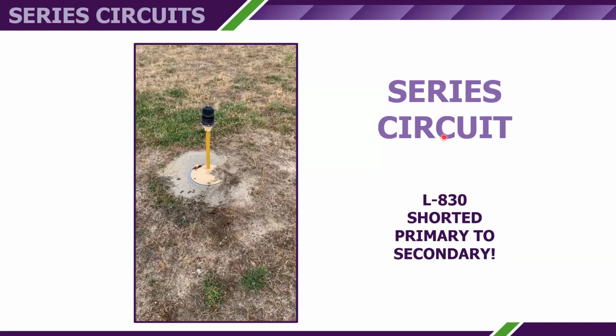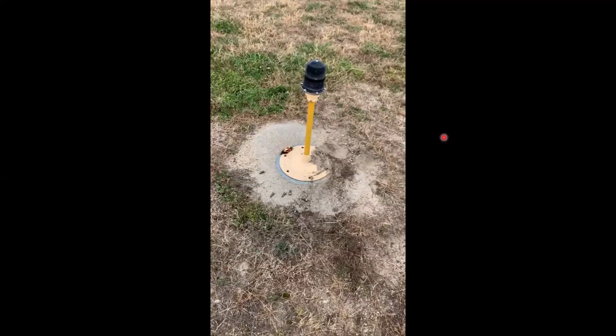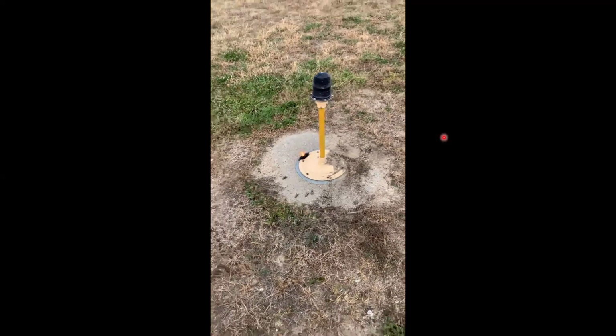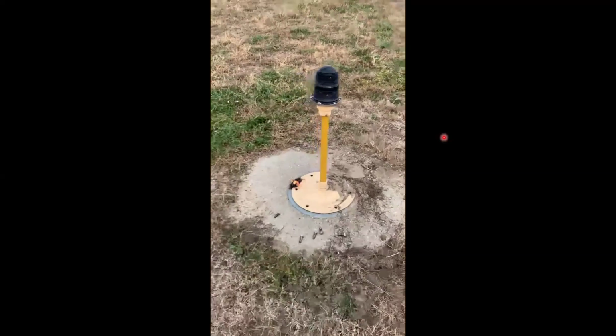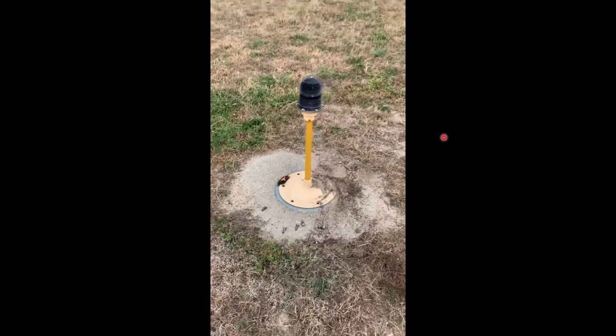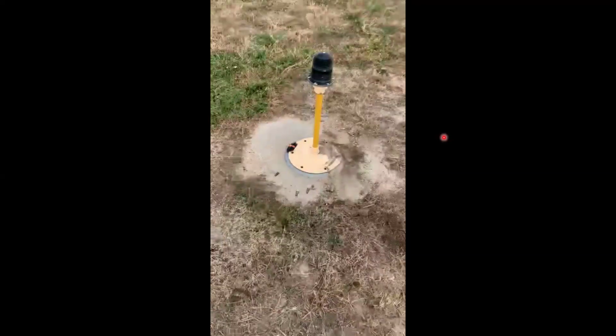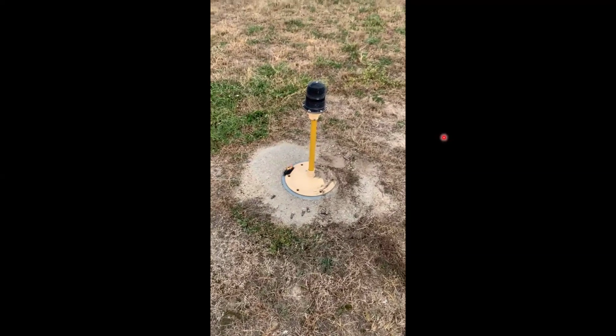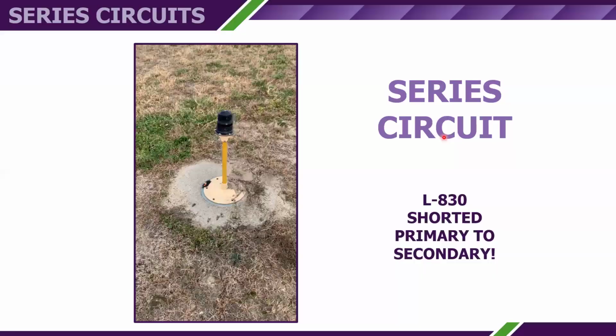The constant current regulator is trying to maintain current flow. Once the last bolt was removed, the constant current regulator provides sufficient voltage to arc over through the rubber gasket between the base plate and the base can. There's a second ground in the system so that current flow can be maintained. So it basically created enough of an arc to burn through the gasket and cause the current to flow between that base plate and the base can.